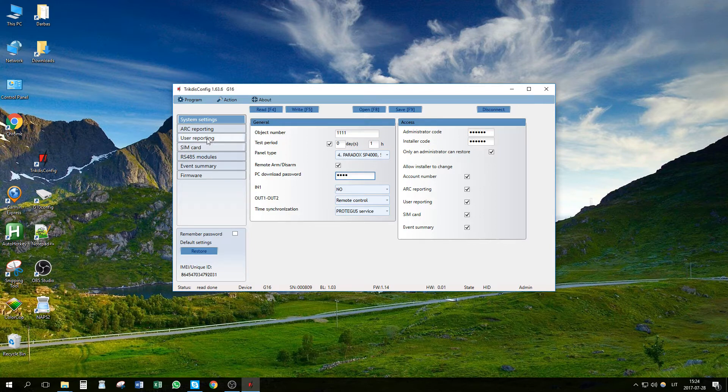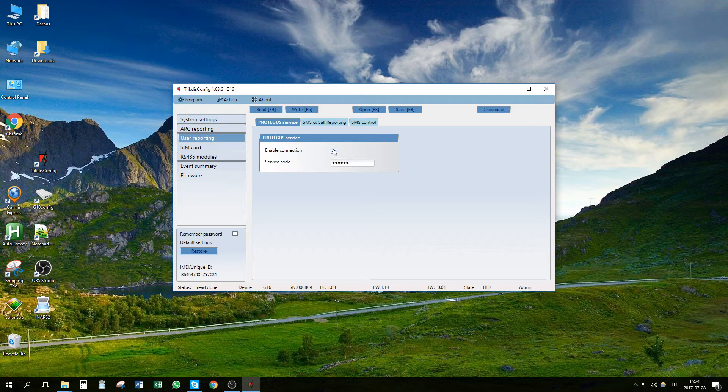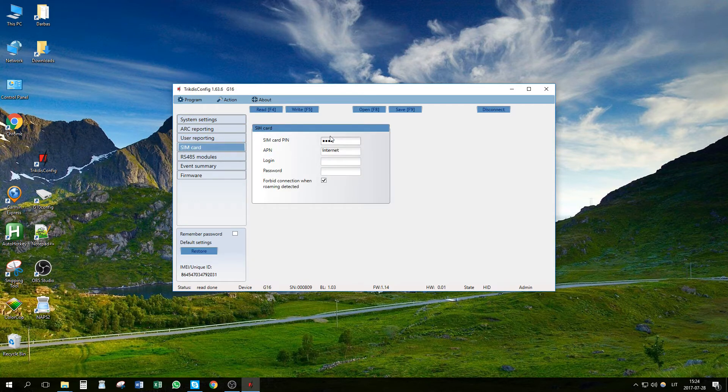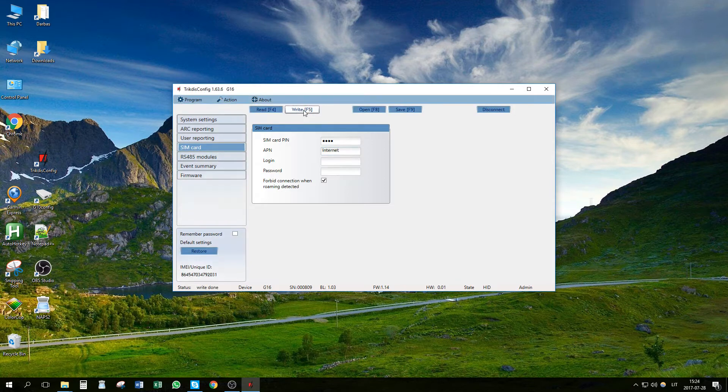Go to User Reporting window and select Enable connection for Protegus service. Go to SIM card window and enter the SIM card PIN code and APN settings. Press the buttons Write and Disconnect.